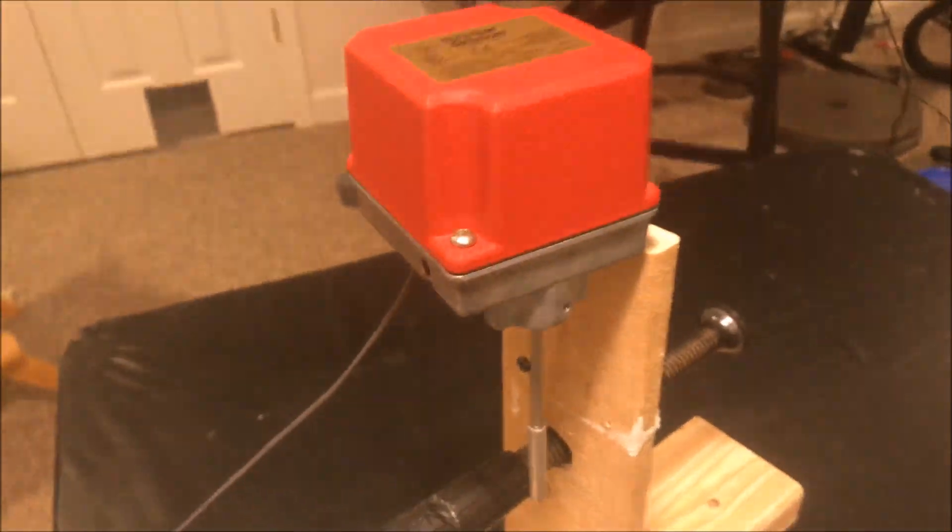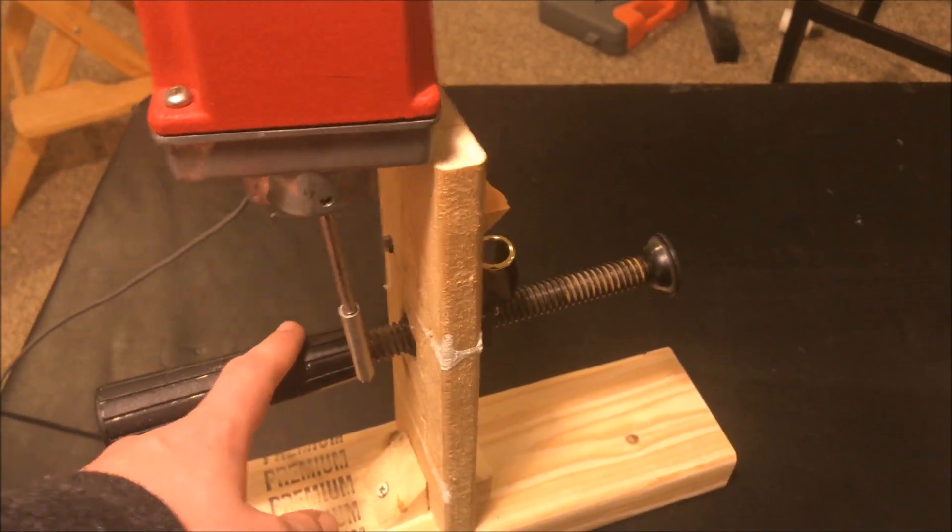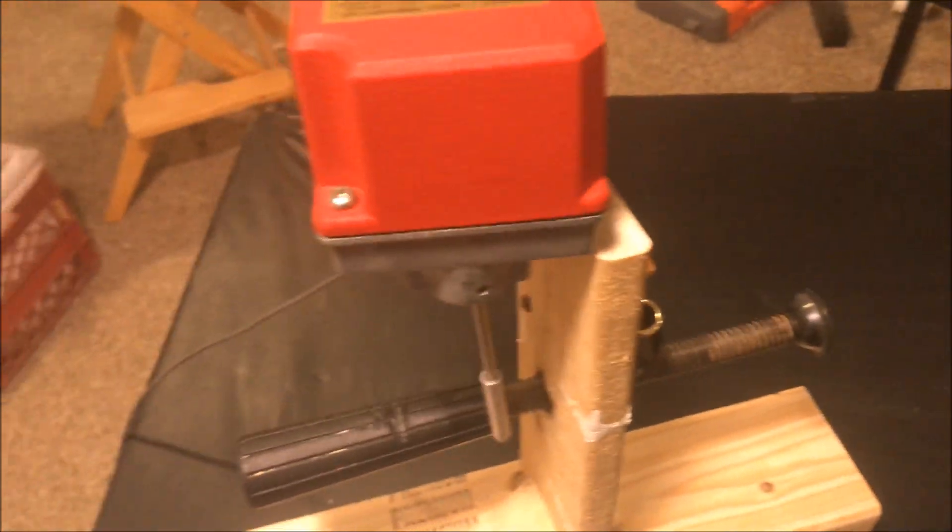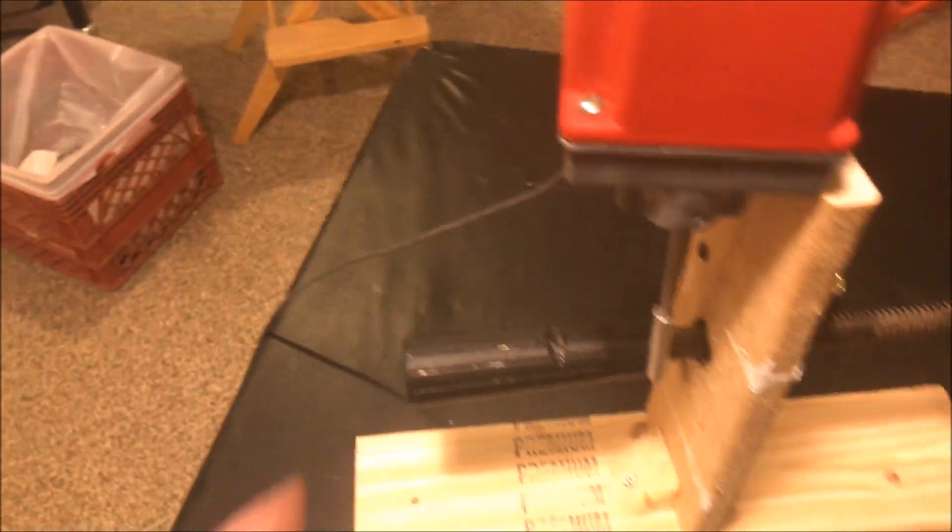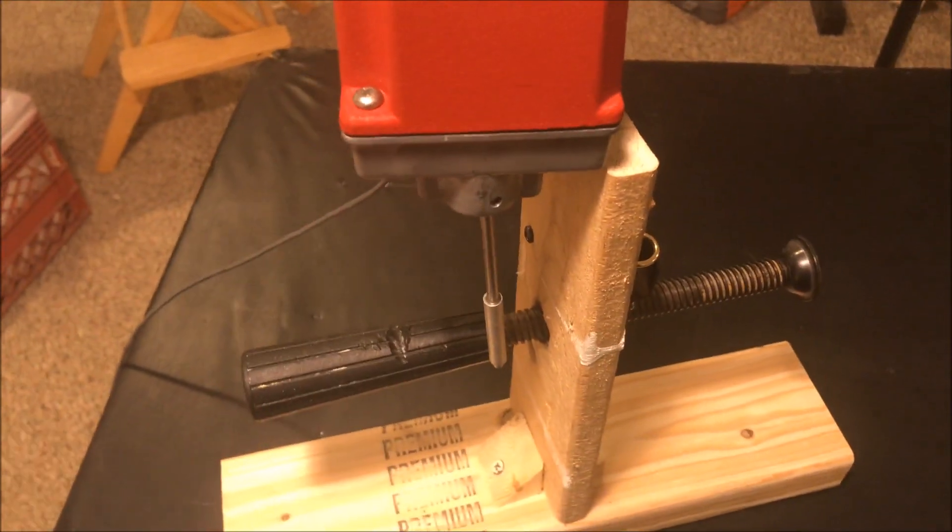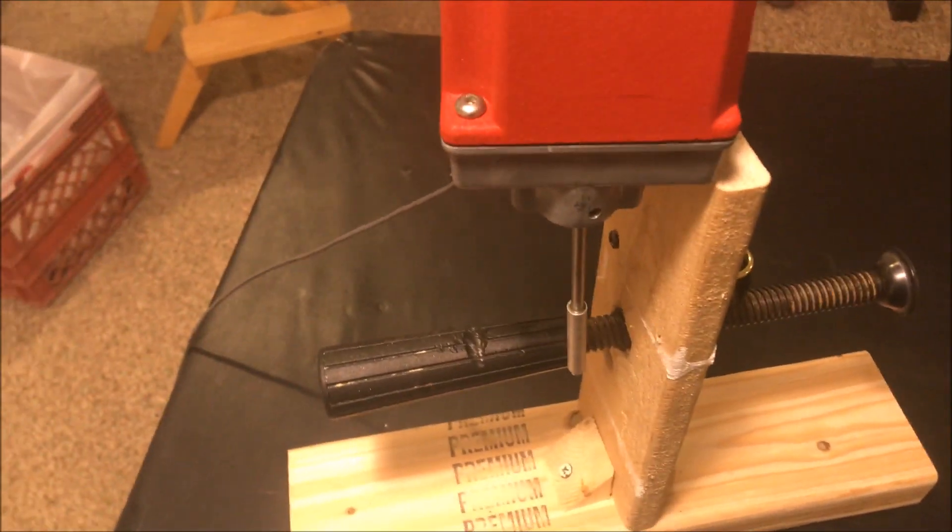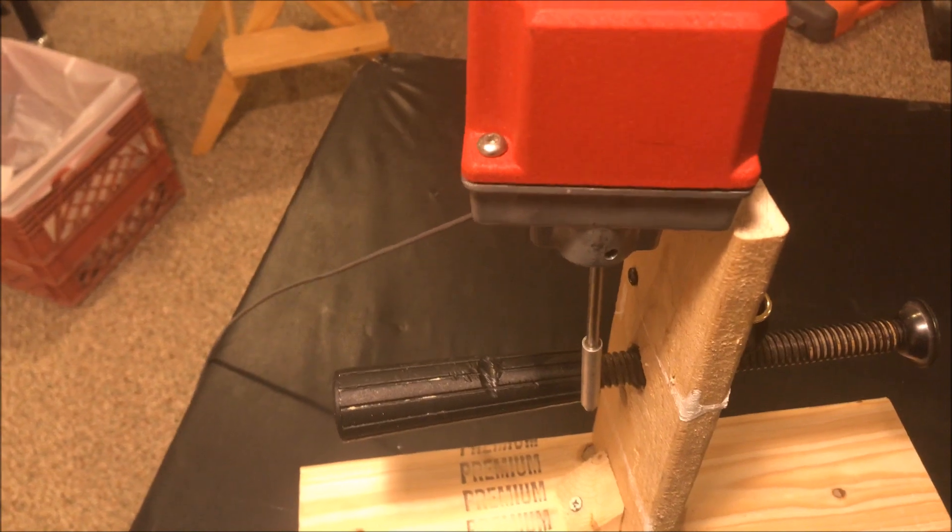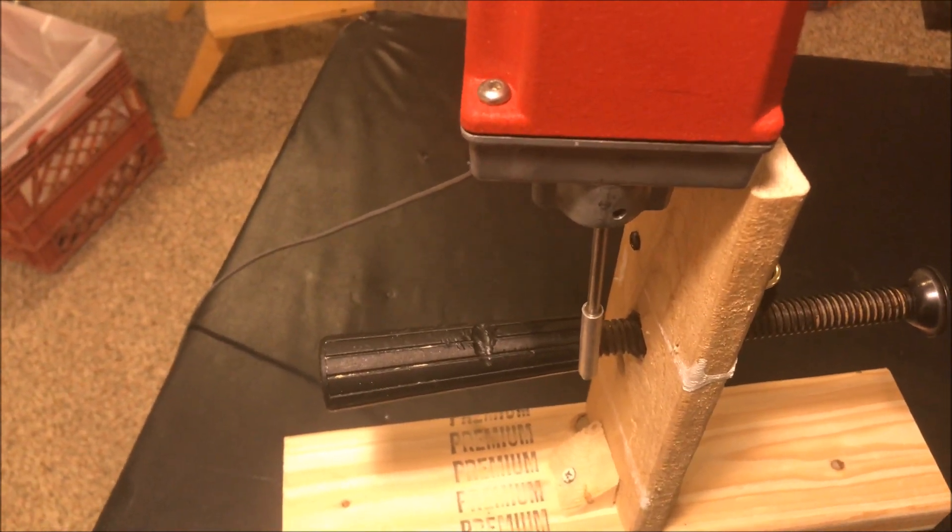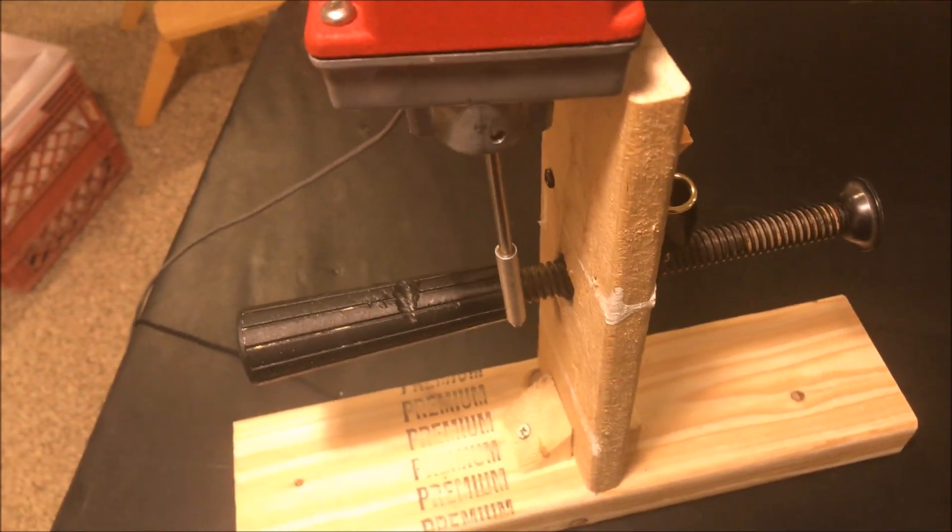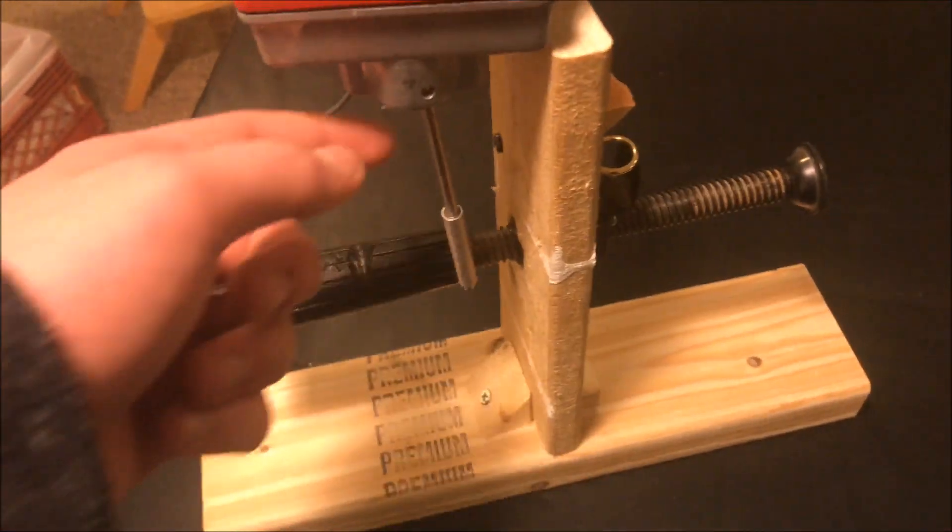Now you can have these set to be either supervising a normally closed valve like this one or supervising a normally open valve which would be the opposite of this. Something like the water shut off to the whole sprinkler system.